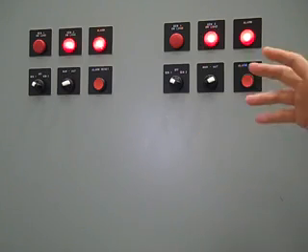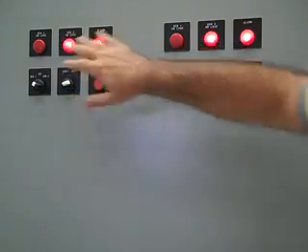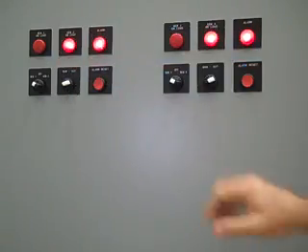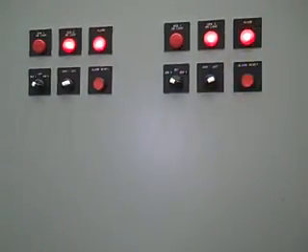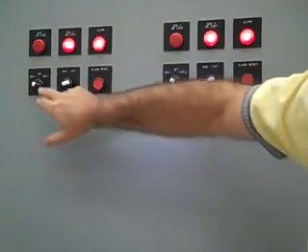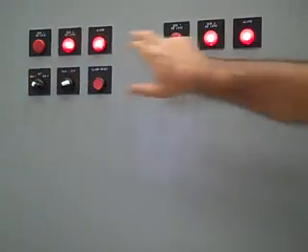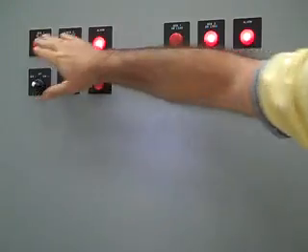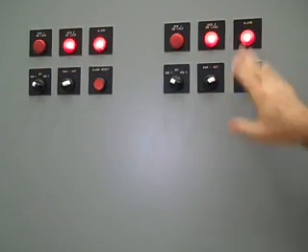And there we go. Because they were already running, it was just that 30-second delay that we have to have. Once it was told to transfer, it told the generator to start. We had the voltage relays already fed, so it went ahead and transferred. And now we have these alarm lights. Okay? So we can see that generator 1 is selected, was in auto, but we're in Gen 2 and Gen 3, which means Gen 1 had failed, and we are running now, that's why we have the alarm light here.